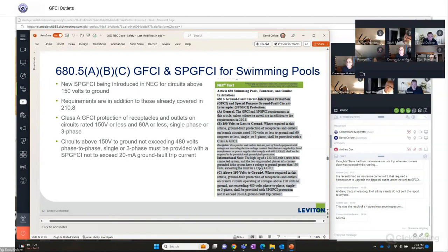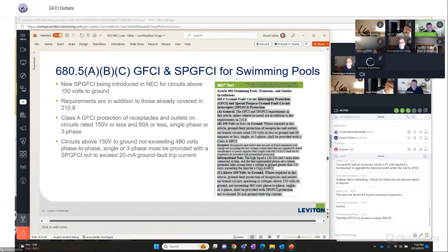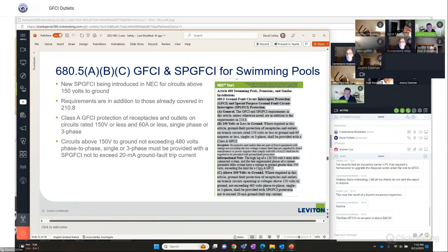And then I had some of this on the code regarding swimming pools, and really what this is doing is it's taking again 15 amp, 20 amp devices, 120 volt, and they're really pushing the code to now go after things that are 240 volt and higher, up to 60 amps and less. So what they talk about in this article is an SP GFCI. So that's a special purpose GFCI device.